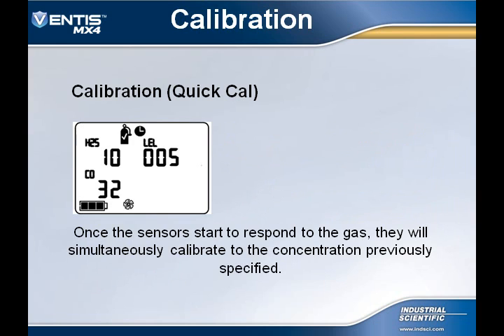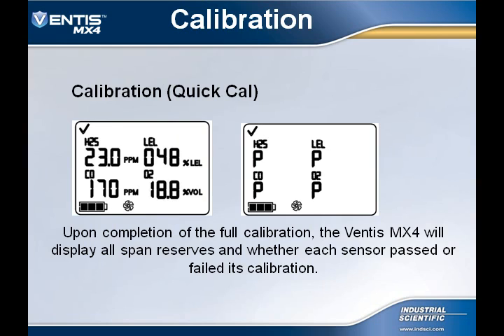At this time, you will see all sensor readings start to increase and respond to the gas. Once the full calibration is completed, the Ventis MX4's display will toggle between all span reserves and a P for pass or an F for failure for each individual sensor.